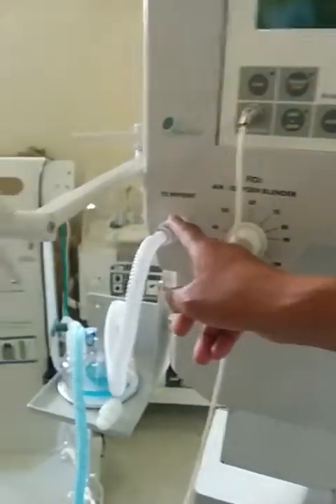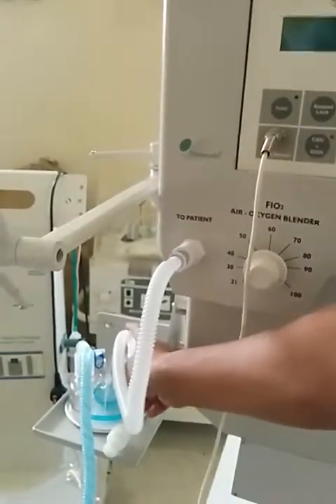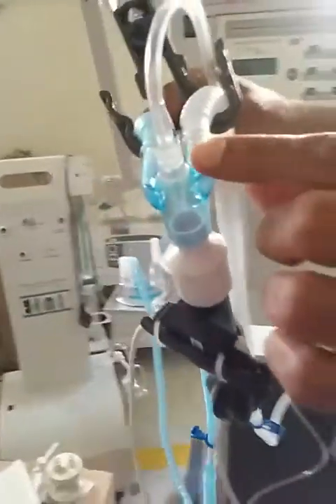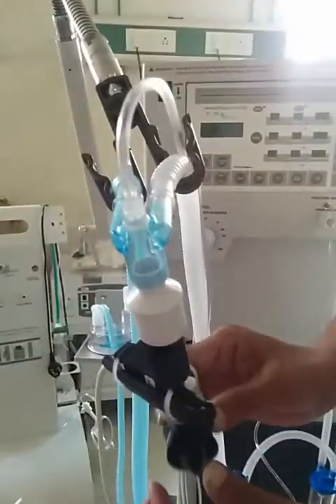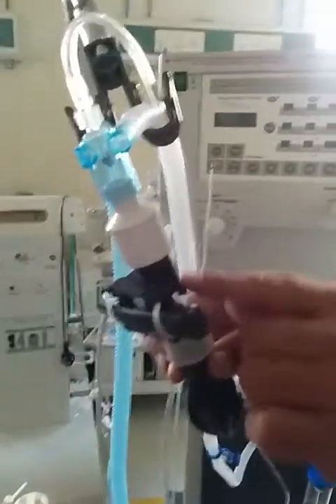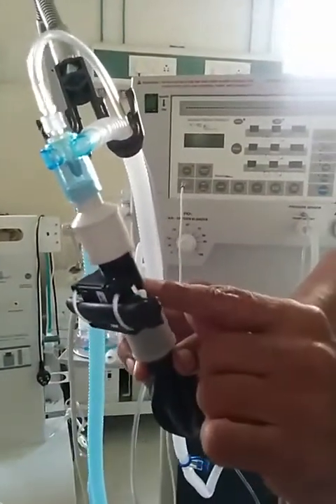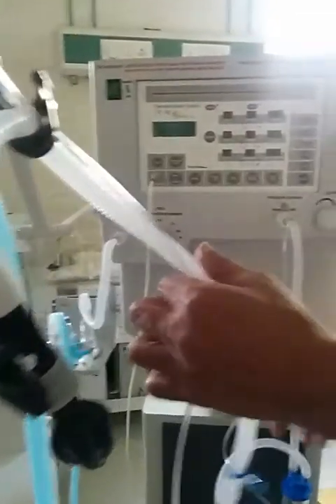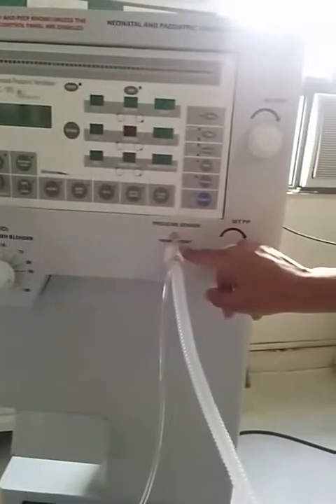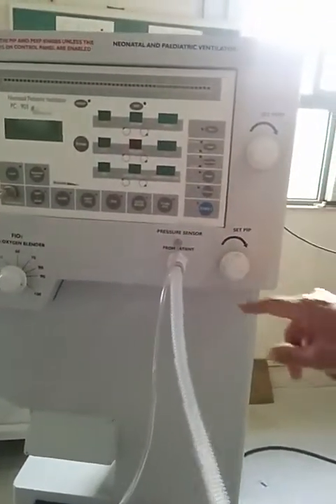These two patient limbs have to go to the humidifier. From the humidifier, it will go to the inspiratory limb. And then at the Y piece, you connect a test lung. Here is your flow regulator, flow sensors. And this expiratory limb goes to the machine again, from where you can set the positive end expiratory pressure.